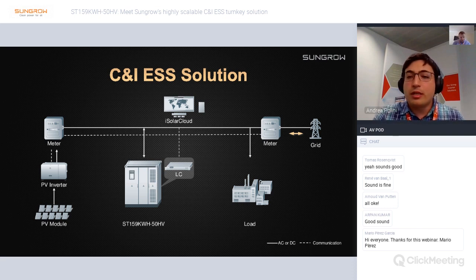For example, here the ESS system may be working in maximizing self-consumption mode. The first energy meter measures the energy produced by the PV inverter and reports it to the local controller. The second energy meter measures how much energy is being bought from or injected into the grid. Based on this measurement, the local controller is able to compute how much power is being consumed by the load.